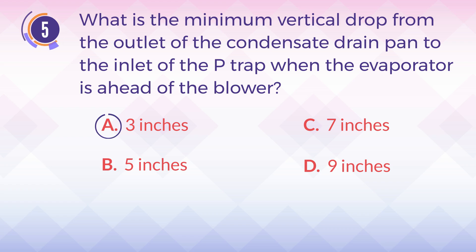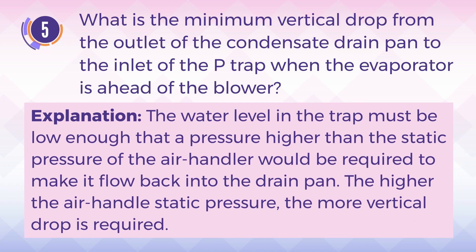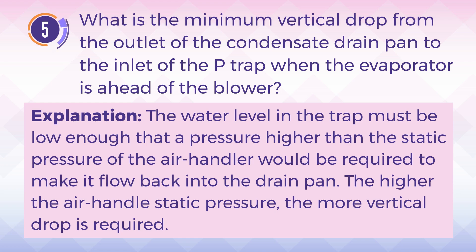The answer is A. 3 inches. Explanation: The water level in the trap must be low enough that a pressure higher than the static pressure of the air handler would be required to make it flow back into the drain pan. The higher the air handler static pressure, the more vertical drop is required.